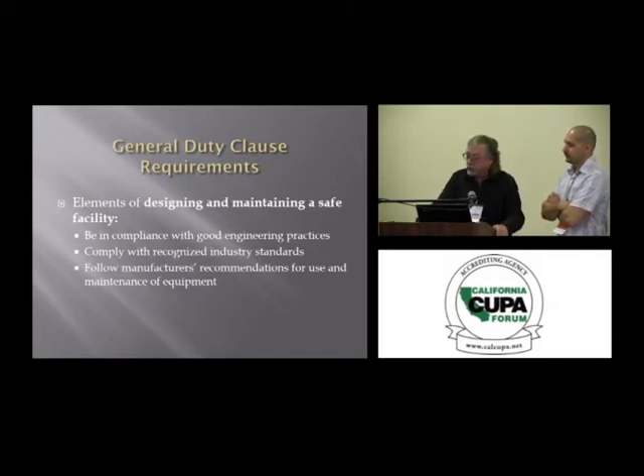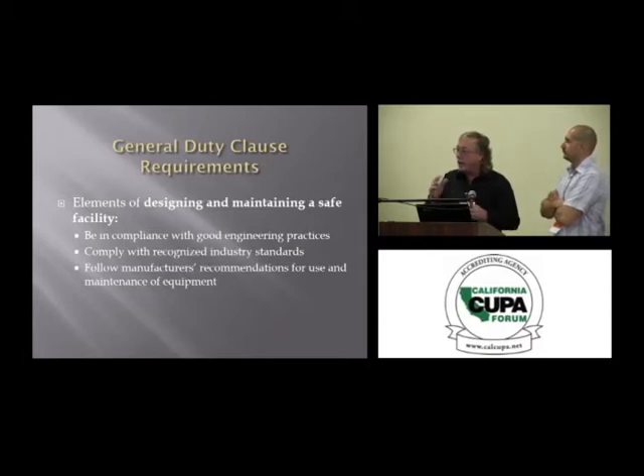And most facilities are doing pretty good. Some are actually doing more than what the manufacturers recommend, and that's a good thing. Some don't follow the IIAR guidelines. They have their own program. But if they can prove that they're keeping their system as safe and mechanically sound as what the guidelines are telling them to do, they're probably doing most of them or exceeding those guidelines.